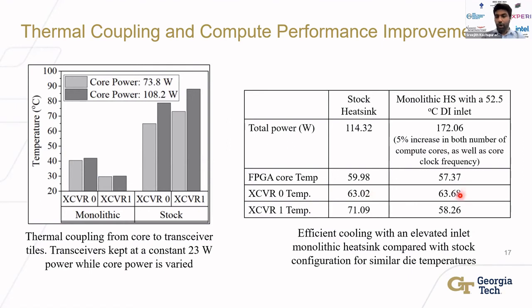Since this was an open-loop measurement, we also evaluated performance in a closed-loop scenario using an elevated inlet temperature. The idea is that if we can maintain good thermal performance at higher inlet temperatures, cooling efficiency improves because less energy is needed for refrigeration or heat exchange. Results showed we could dissipate much higher power while maintaining similar thermal operating points even with an elevated inlet temperature coolant.